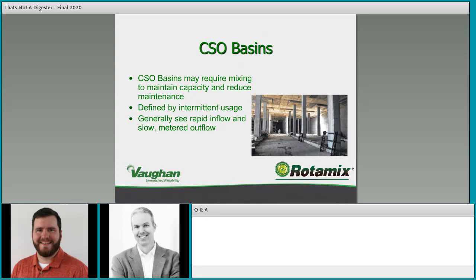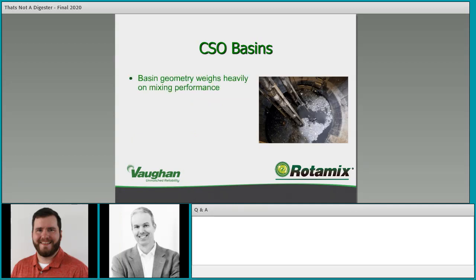Grit and debris are the main concerns for mixing design in CSO basins. If you have to go in and clean them out, it's generally a confined space entry — a very expensive endeavor requiring specialized equipment. Basin geometry weighs heavily on mixing performance. We prefer vertical shafts, as they generally outperform large shallow basins. The mixing design must provide adequate velocity to suspend grit and debris across the entire floor area.